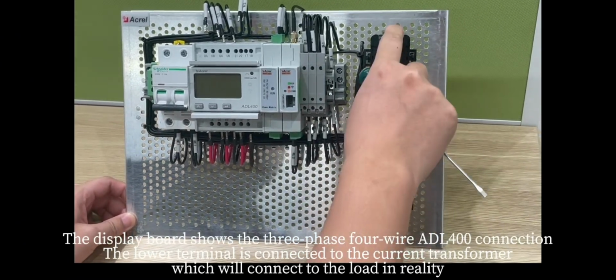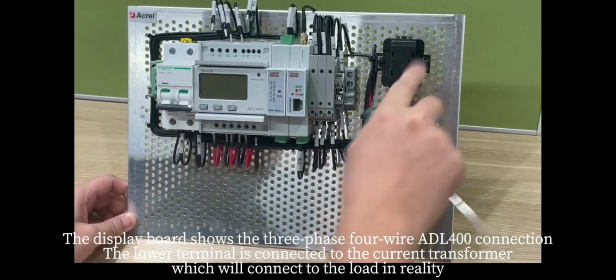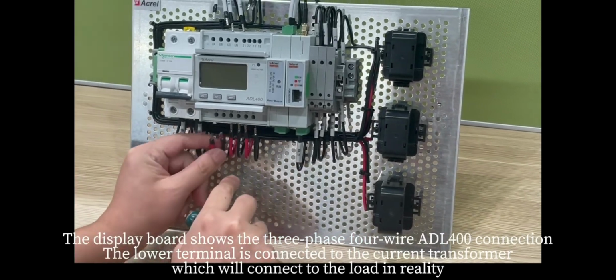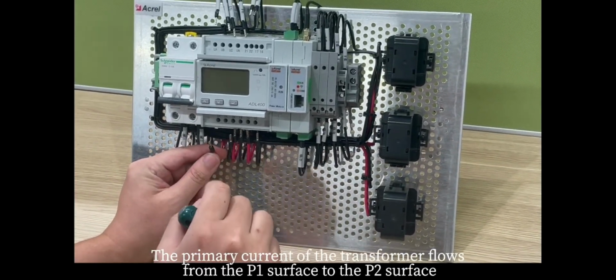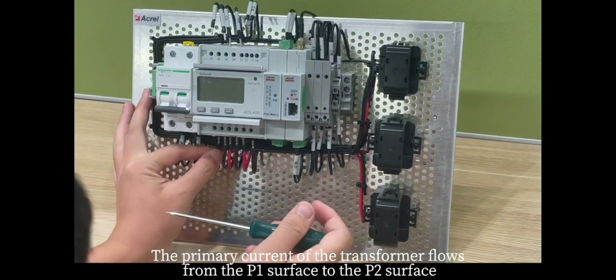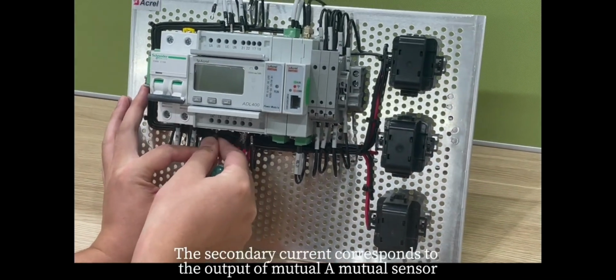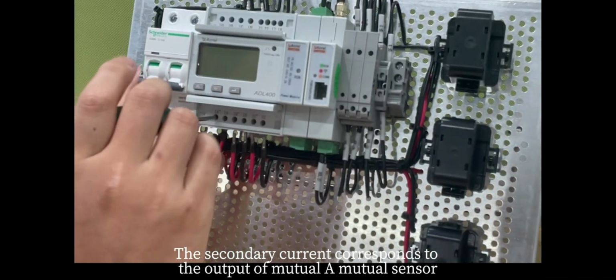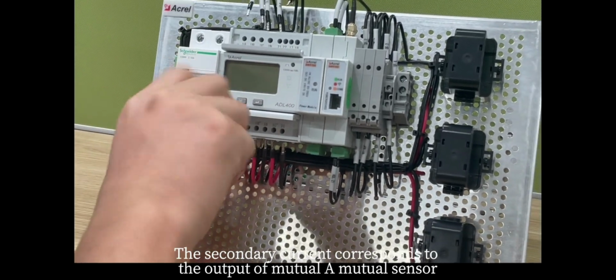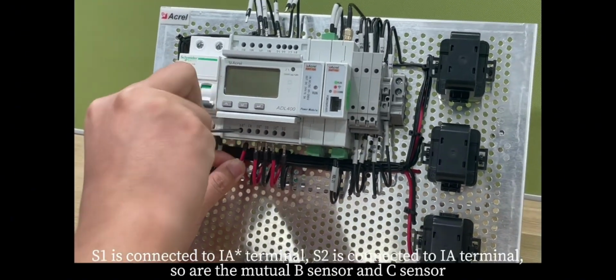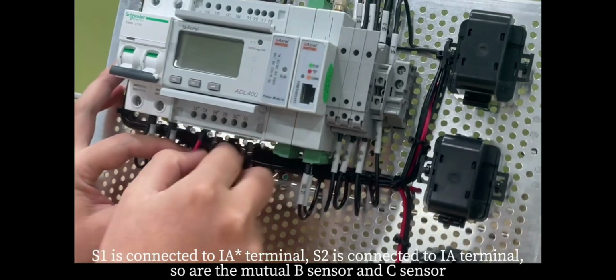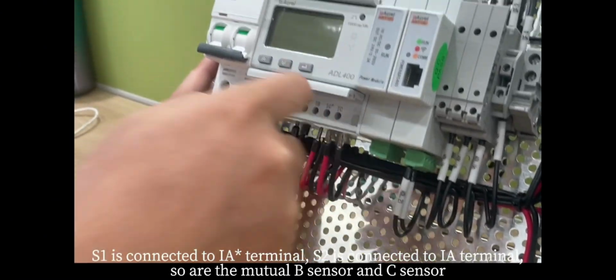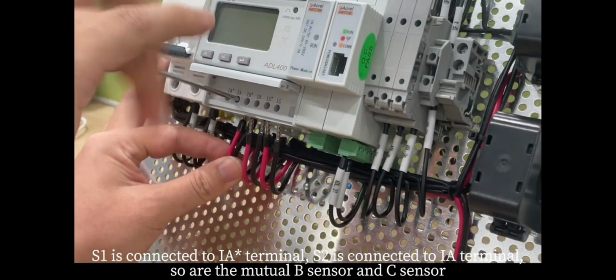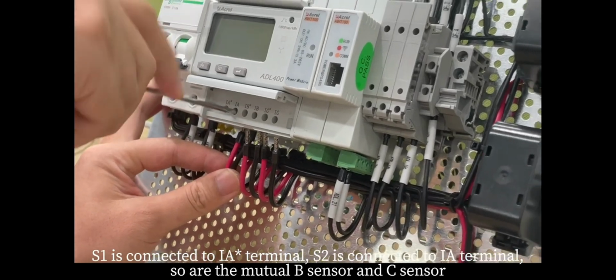The lower terminal is connected to the current transformer, which will connect to the load in reality. The primary current of the transformer flows from the P1 side to the P2 side. The secondary current corresponds to the output of the A current sensor. S1 is connected to the IA positive terminal, S2 is connected to the IA negative terminal, and so are the B sensor and the C sensor.